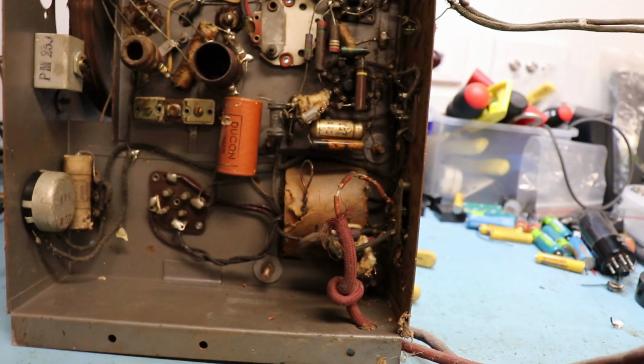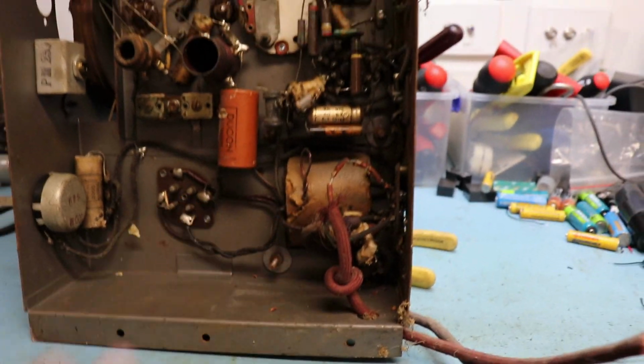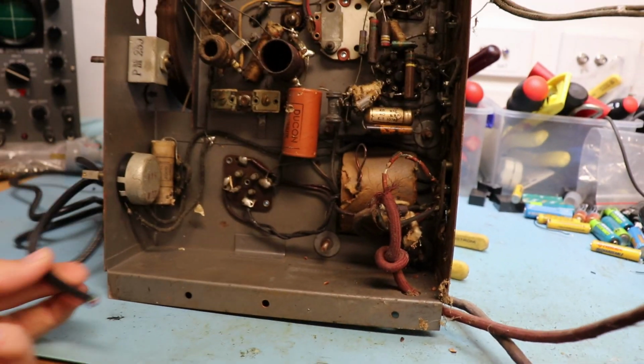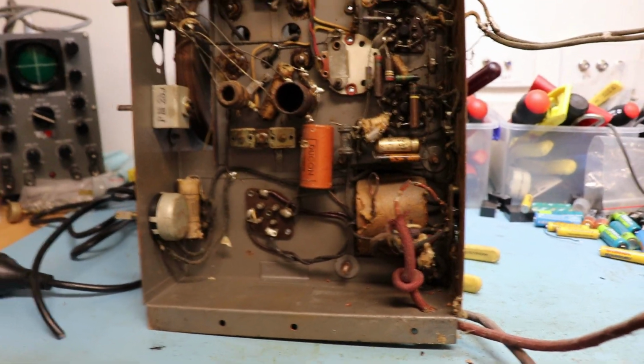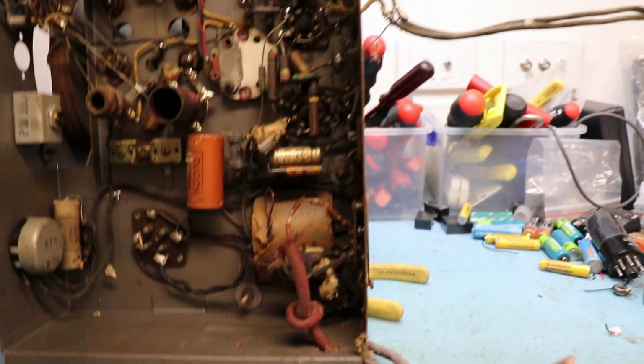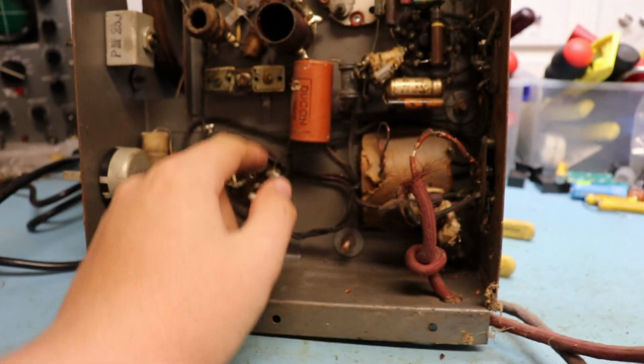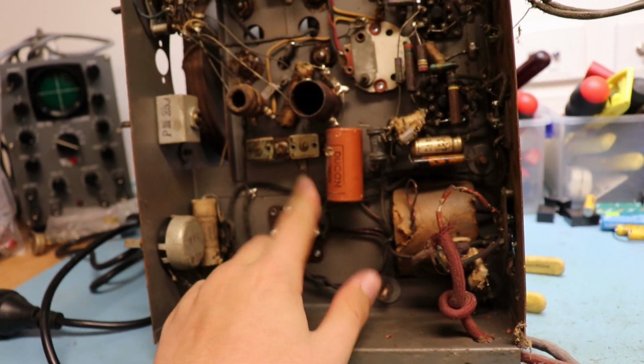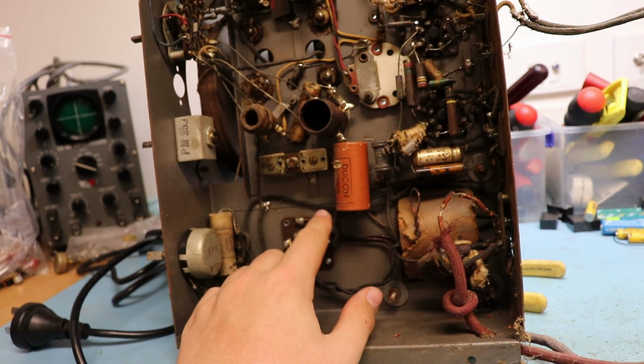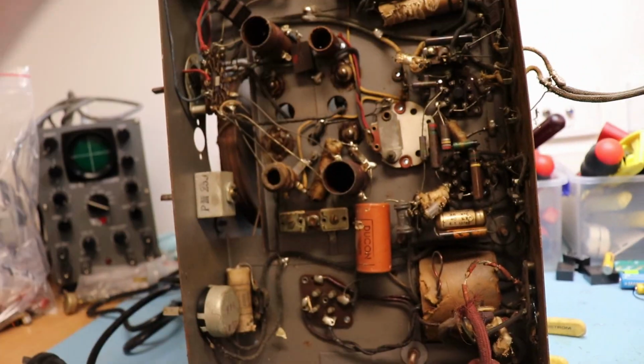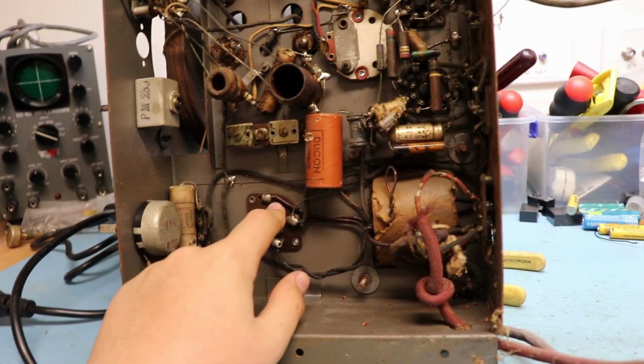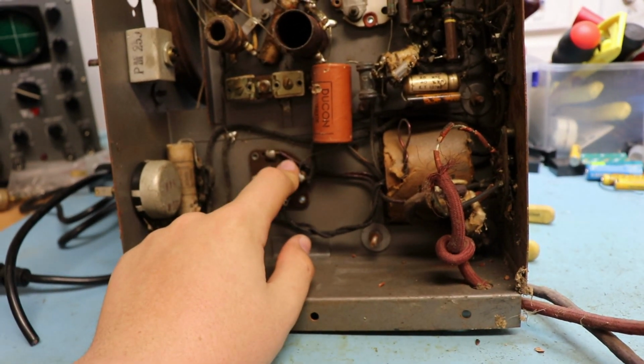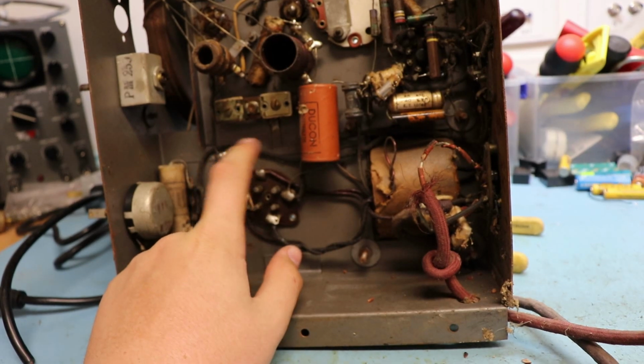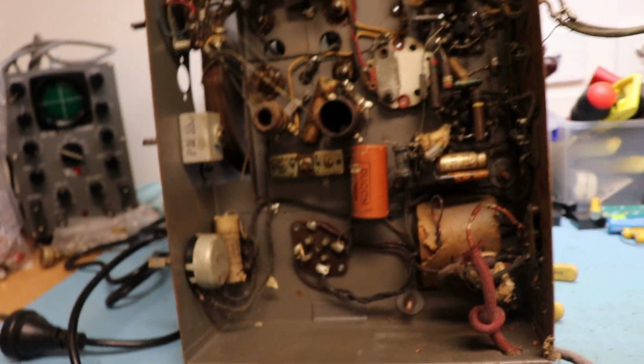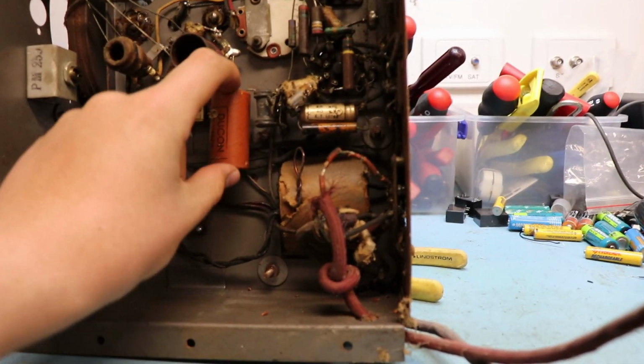So first thing I'll do is make sure the transformer's not shorted. Then I'll replace the power cord and start recapping. But before that, I'll take the DC high voltage off the rest of the circuit and check what the high voltage is with no load on it, just to make sure the capacitors don't get a bit upset.